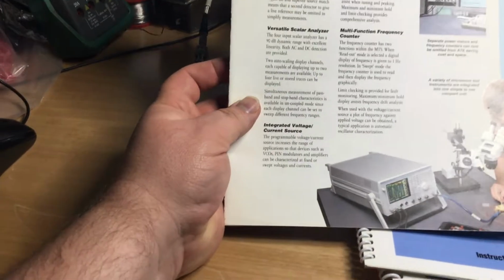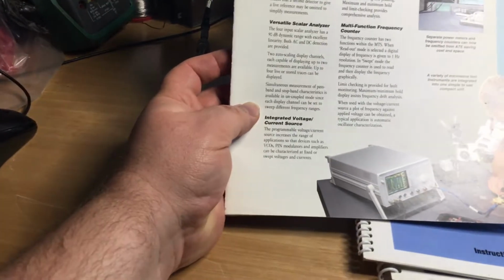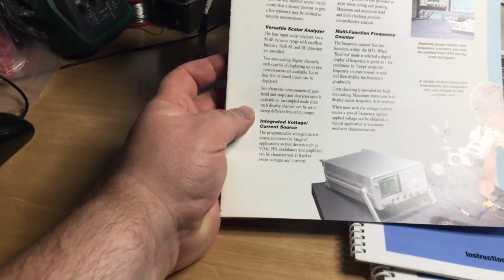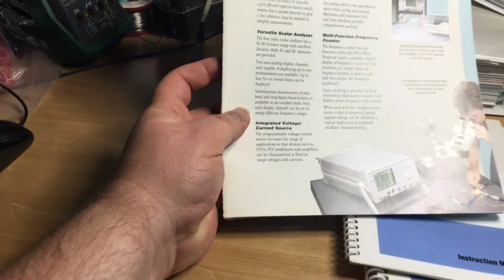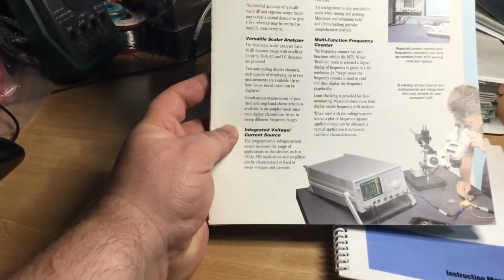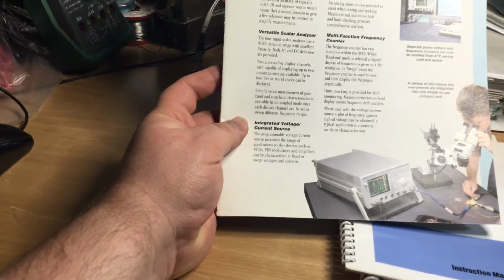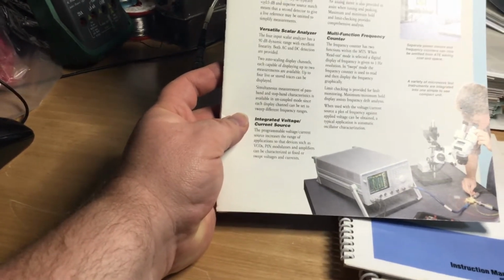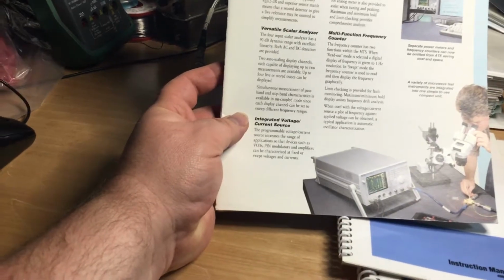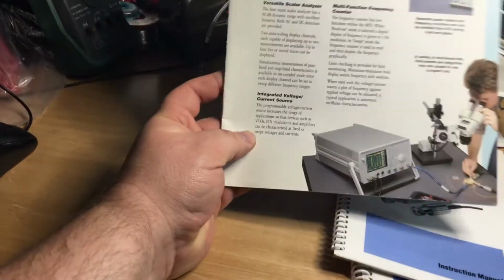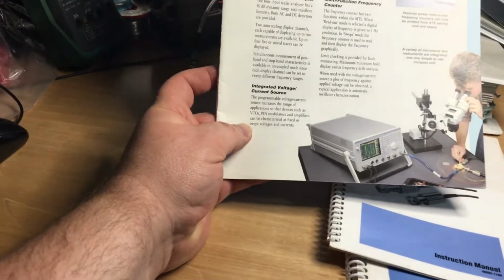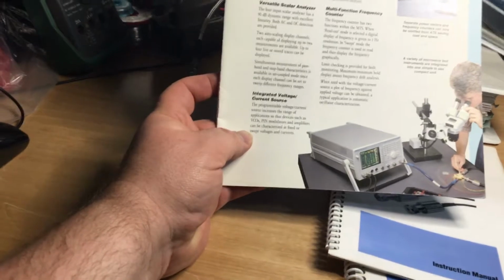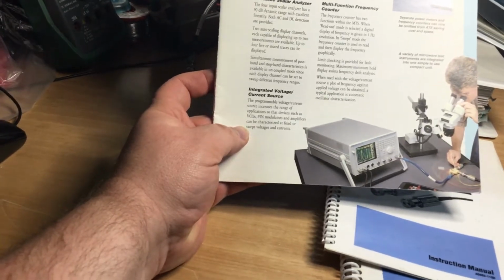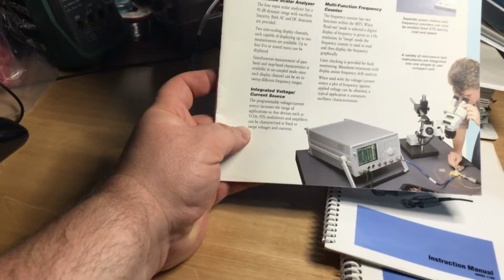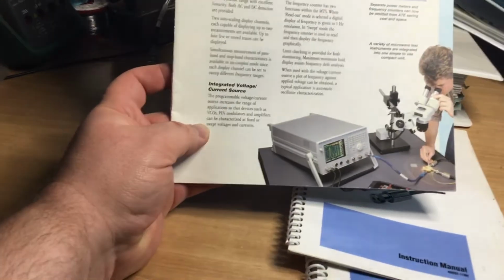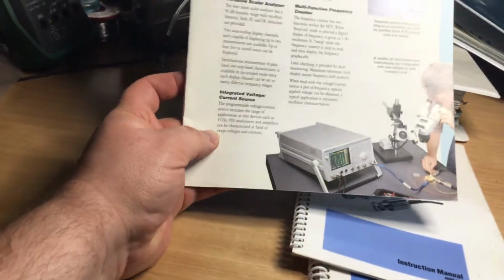Two auto scaling display channels, each capable of displaying up to 2 measurements, are available. Up to 4 live or stored traces may be displayed. Simultaneous measurements of pass band and stop band characteristics are available in uncoupled mode, since each display channel can be set to suit different frequency ranges. It's got integrated voltage and current sources. The programmable voltage current source increases the range of applications so that devices such as voltage controlled oscillators (VCOs), PIN diode modulators and amplifiers can be characterized at fixed or swept voltages and currents.